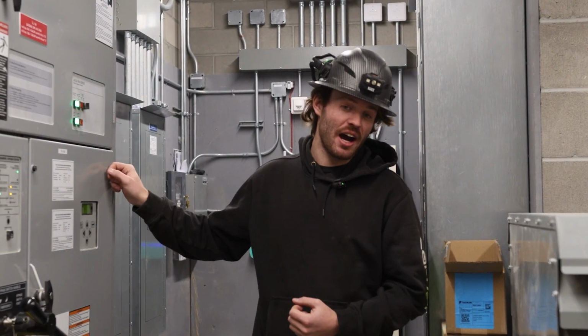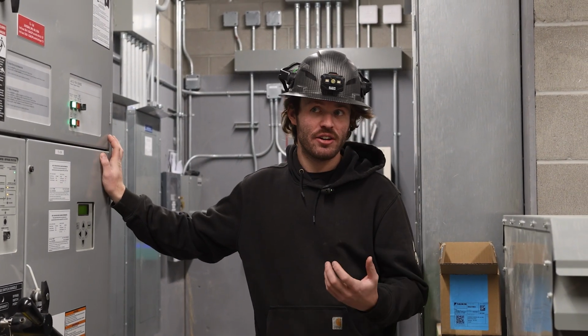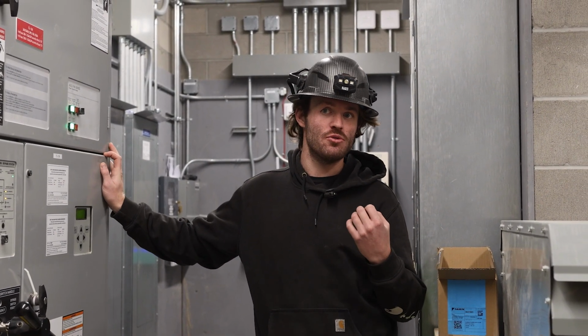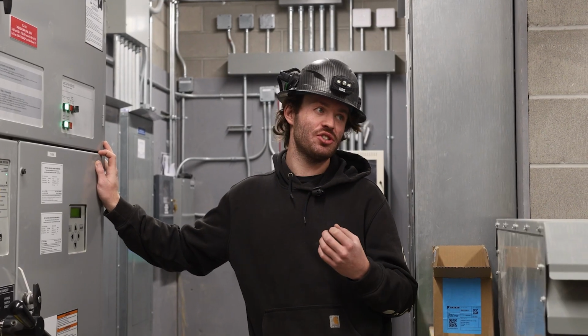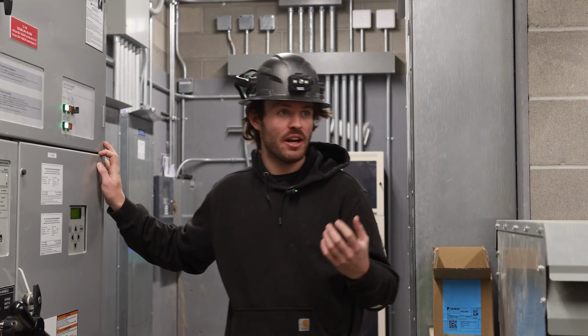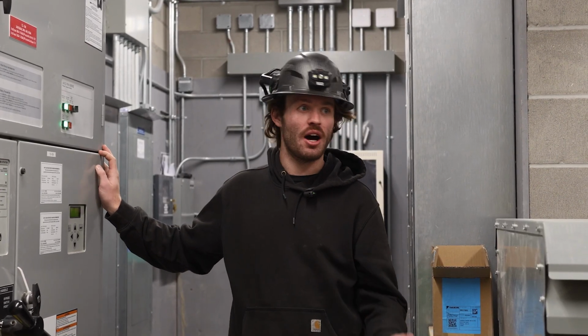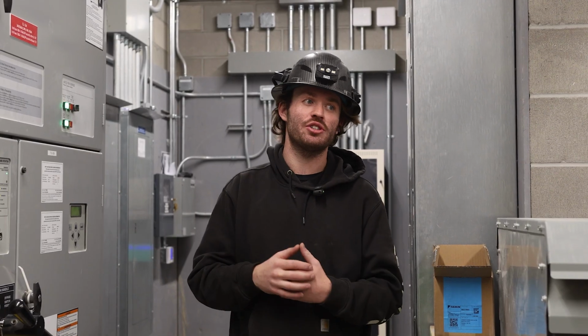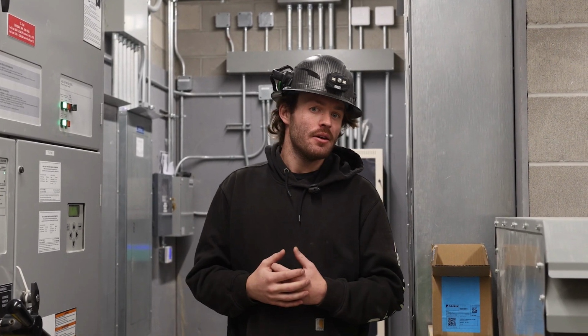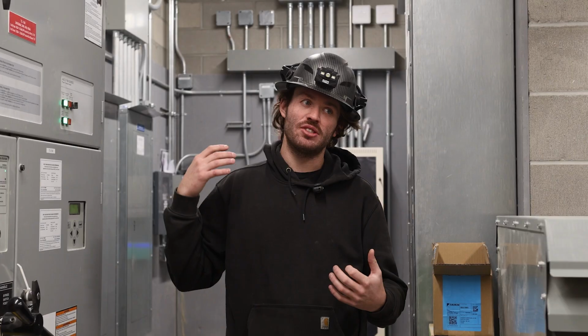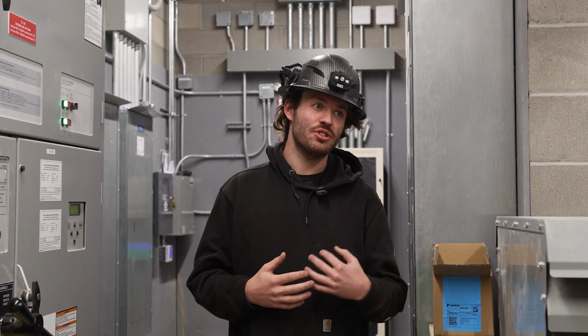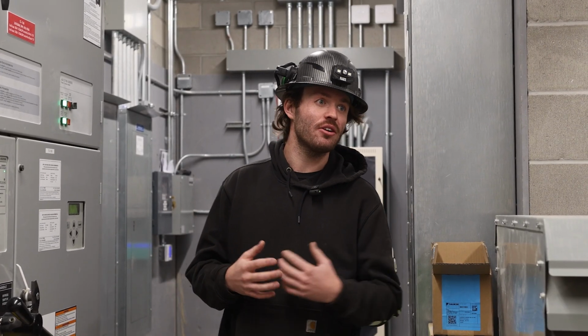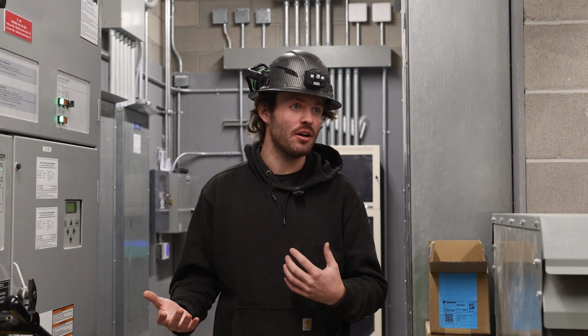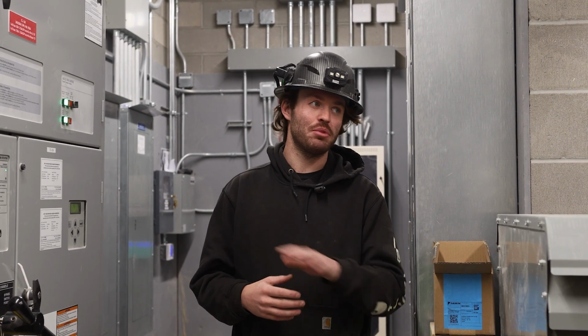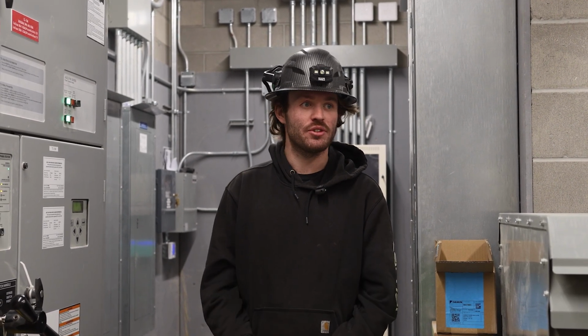A good amount of the time I actually see generators running due to over voltage situations. If our main hydro feed is above a certain threshold, it'll call the generator to start and run. That's a good thing to do because it'll protect motors from over voltage situations, and all the mechanical in the building, it protects from that as well. It doesn't have to be a complete blackout of power for it to want to transfer to the generator.